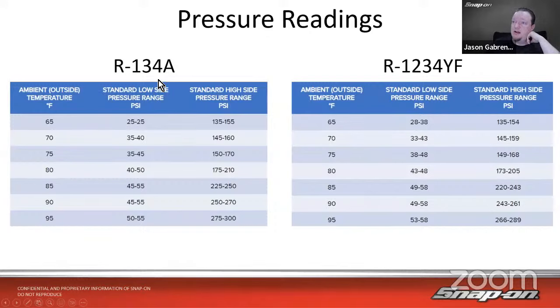So you see, they're fairly close. So if I look at R134A pressure on the gauge at, say, 80 degrees, which it is right now in my house, 40 to 50 PSI on 134A, 43 to 48 PSI on 1234. So it's a little bit closer of a window, but it's pretty close. And then on the high side, 175 to 210, 173 to 205, right? We're within like 1% or 2% as far as the pressures are concerned. So your rule of thumb on 134A is probably not going to go entirely out the window with the 1234YF. It's going to be fairly close. But if you want to be really, really accurate with it, you can find those charts online.